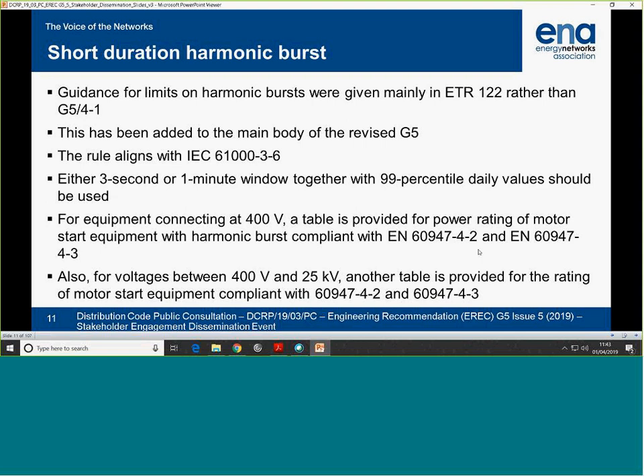And for 5 kV, which is the next voltage level, we provided a table for ease of really applying the rules. Bruce, is there any reason why you went from the 95th percentile values to the 99th percentile? Is there any background behind why that changed? Yeah, but this is only for short burst equipment. Right. We still adopted the 95th percentile for general compliance assessment. Right, yep, okay.